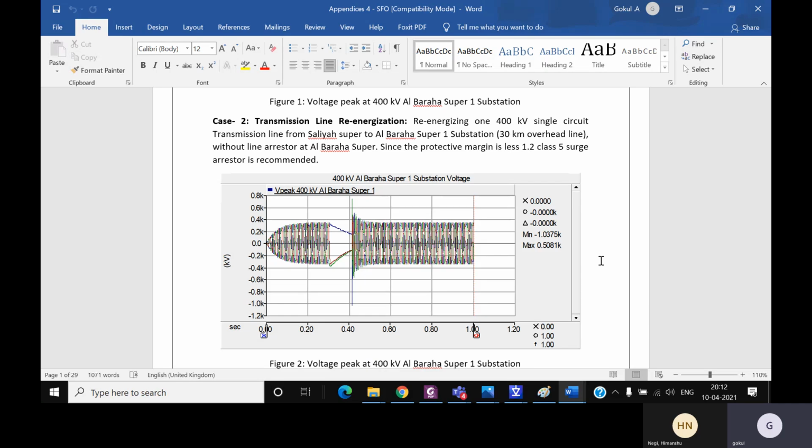So you have to do it, and this will always create the worst case, and the time difference should be 100 milliseconds. I'm going to open it at 0.3 and close it at 0.4. Look at these three plots: it goes toward zero, but before even reaching zero we are turning it on, energizing again.